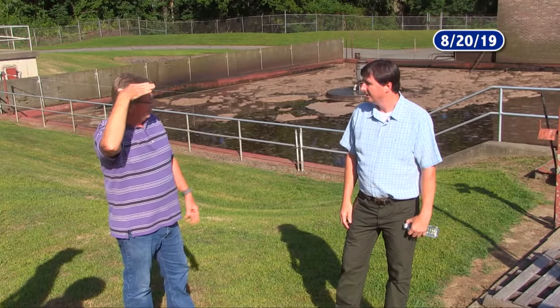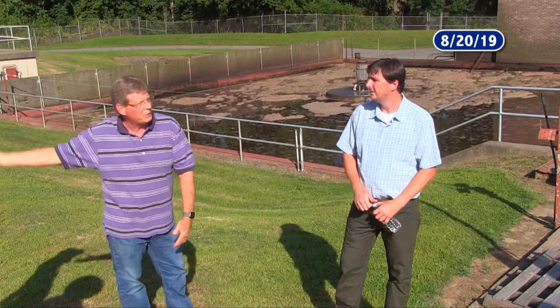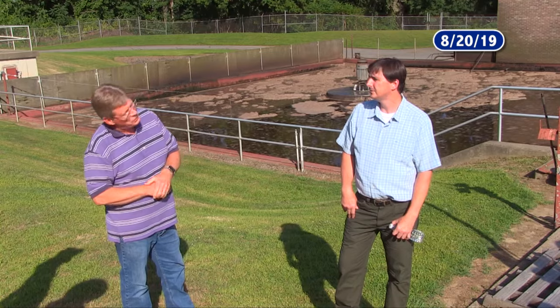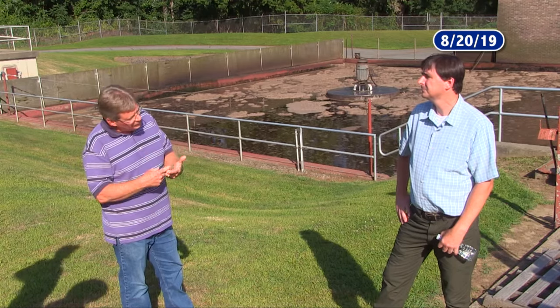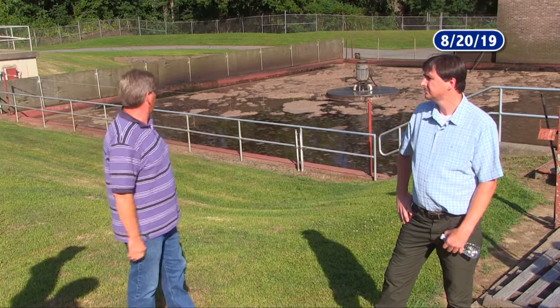Yep. The grinder is great if you're in a pumping station somewhere out there, and it grinds it up preliminarily, so now it's small pieces that won't clog the pipe. But in a plant, all you're doing is grinding the trash up if it's sharp. And it doesn't stay sharp for very long. And then it's passed through right into the system anyway, along with all the grit, it scours out all the pipe and wears out all the parts. And the impellers get sandblasted in it.